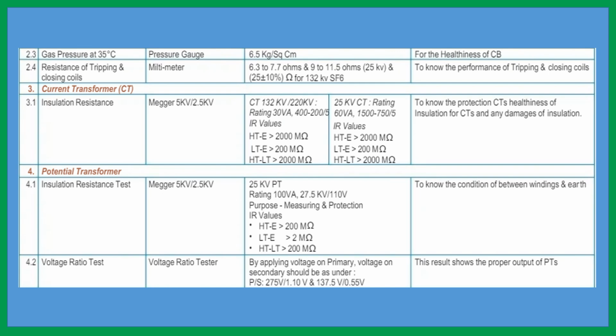Ratio is 1500 or 750 by 5. Okay, two ratios in the primary, 1500 and 750 by 5. It means 5 ampere is the rated load current of the relay, the secondary of the CT. Its values are HT to earth 2000 megohm, LT to earth 200 megohm, and HT to LT 2000 megohm.